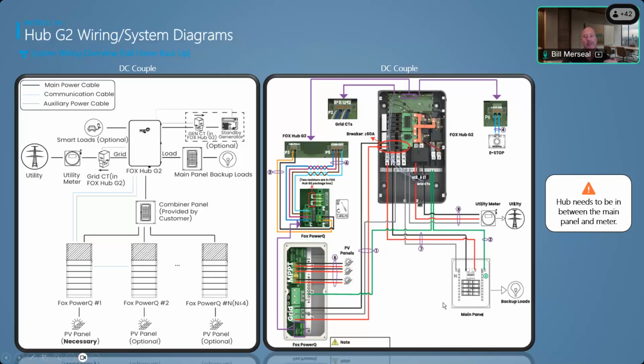So, quick breakdown on how this works. If you go to the far left in the middle of the page, you're going to see utility. We'll map this out very quickly. That utility goes to your main meter in the house. So if we're doing a whole home backup, in this case a DC coupled system, we're going to run your utility meter right into the hub. You'll see here that L1 and L2, the red and black, that's where your CTs - those are the grid CTs.